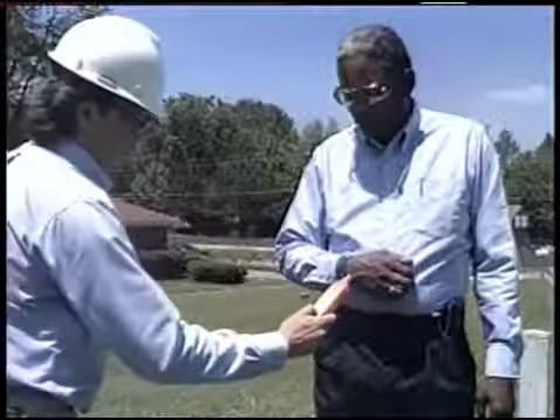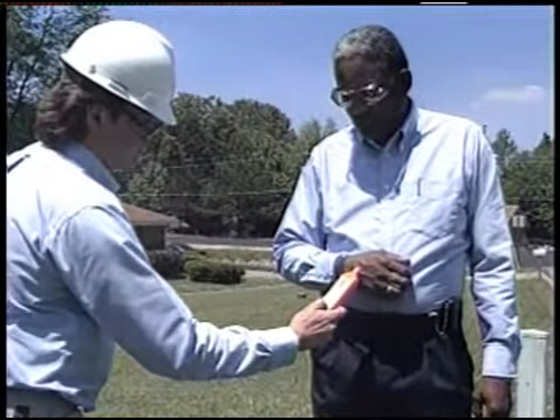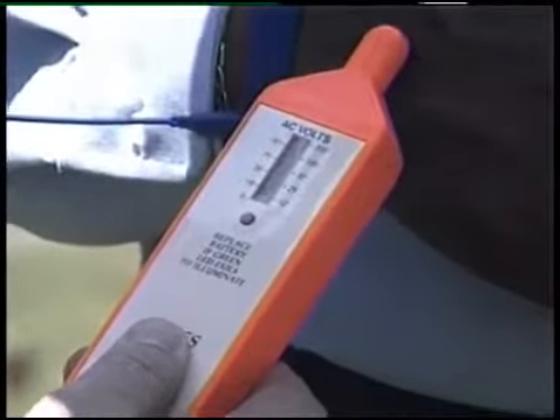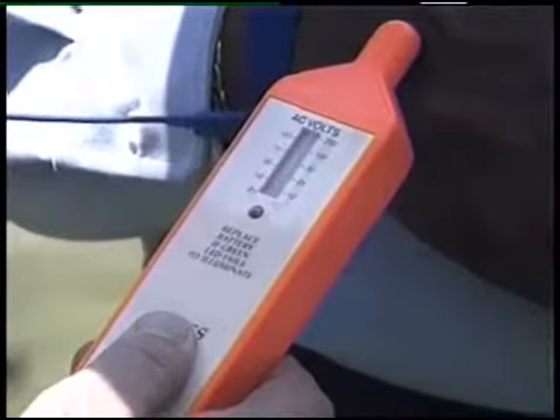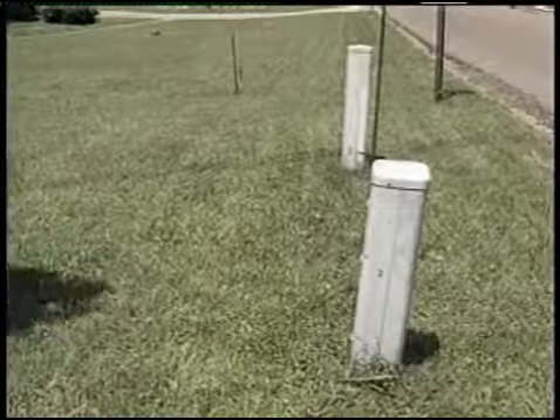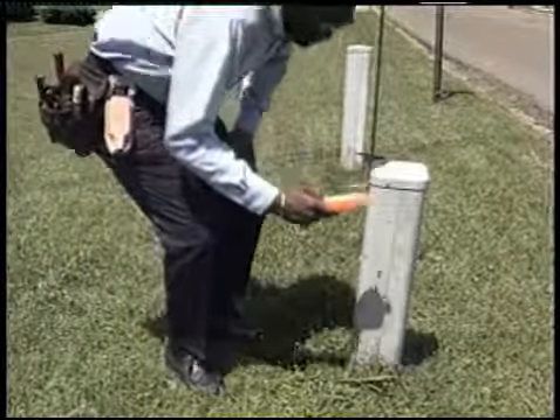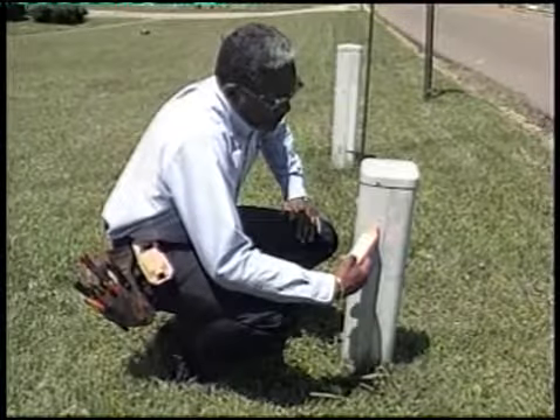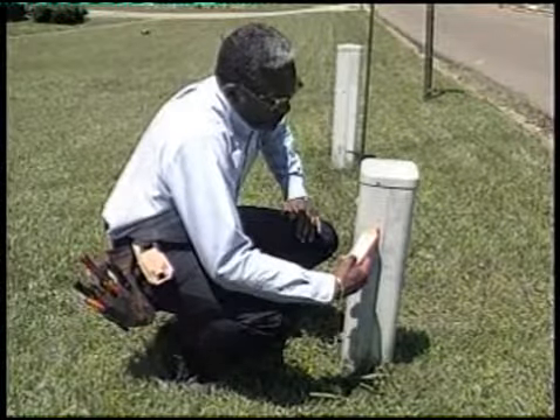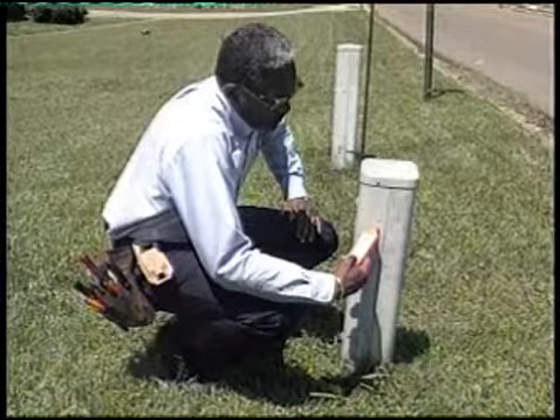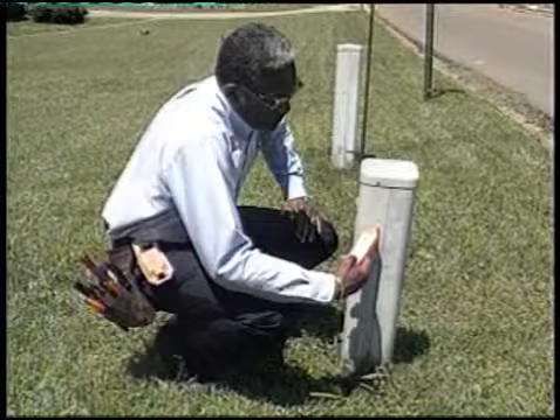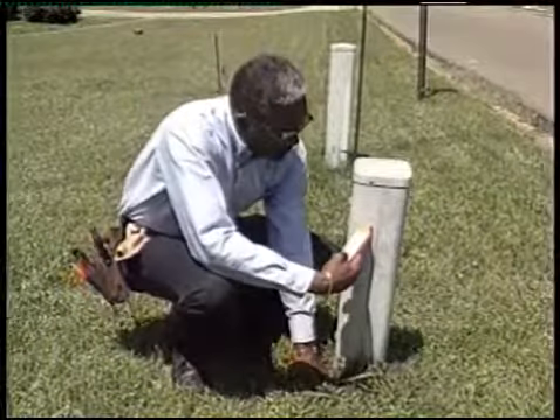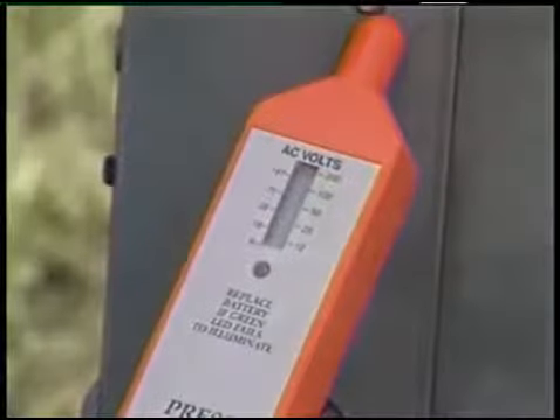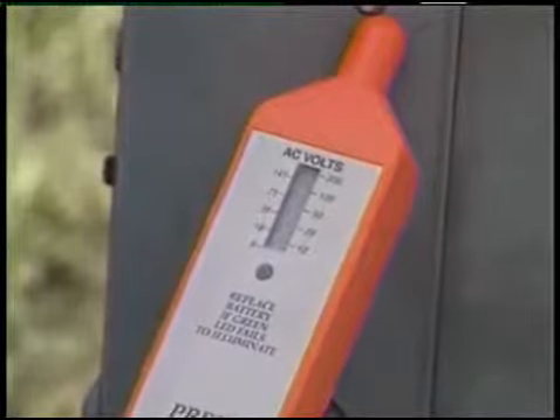They are also very easy to remove. Watch what happens to the indication on my partner when we connect him to a simple ESD wrist strap that is grounded. The same thing happens when he contacts anything that is conductive and goes into the earth. This same phenomena will give an apparent false indication when we test a grounded object, such as this pedestal, if the operator is not grounded. The best way to overcome this is for the operator to ground himself by any safe means at his disposal and test the pedestal or cabinet.